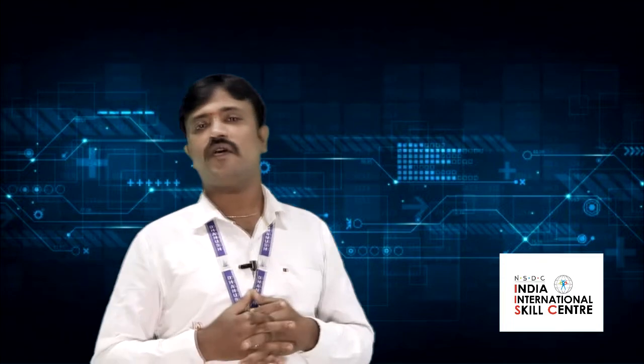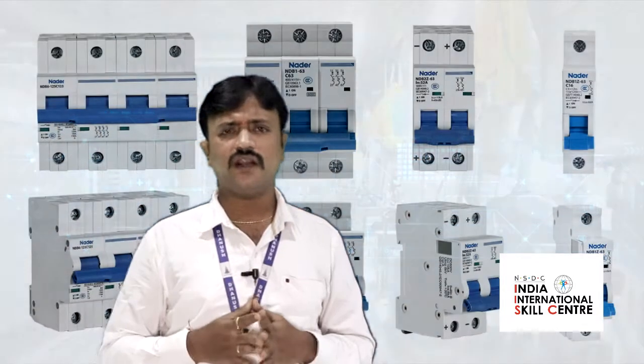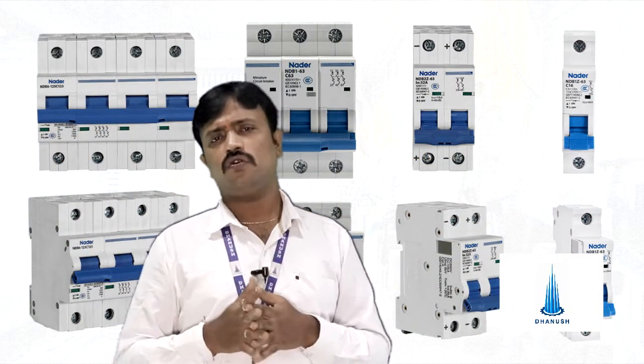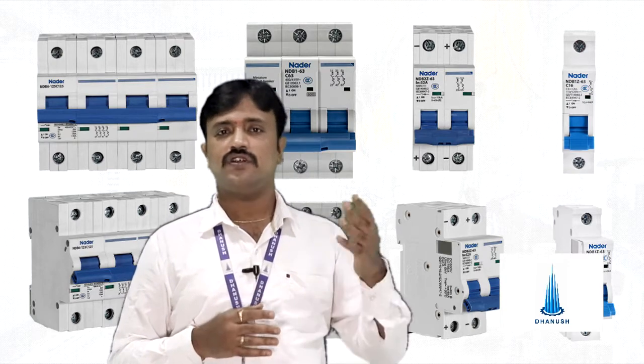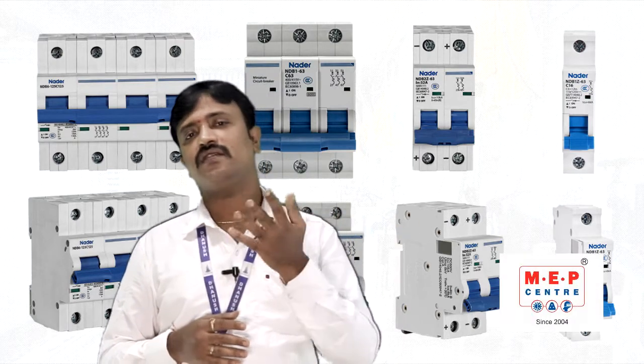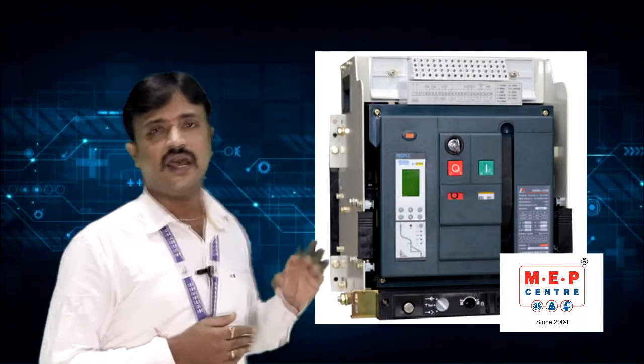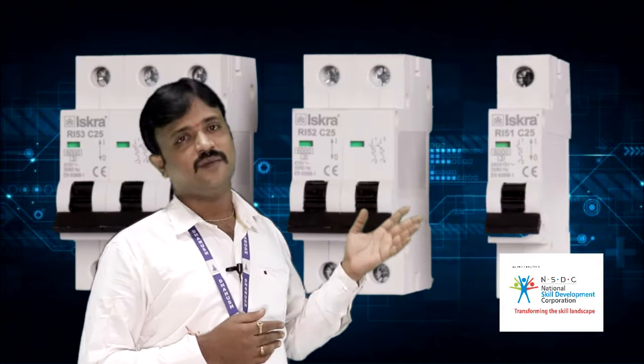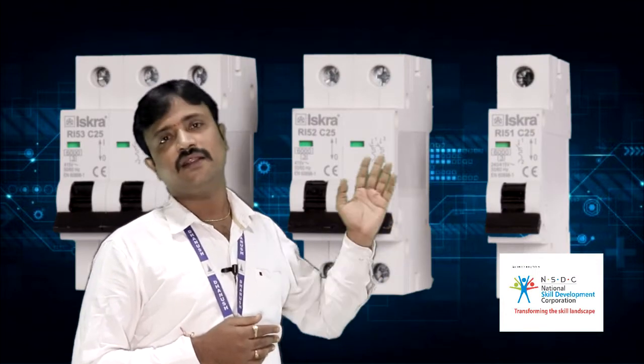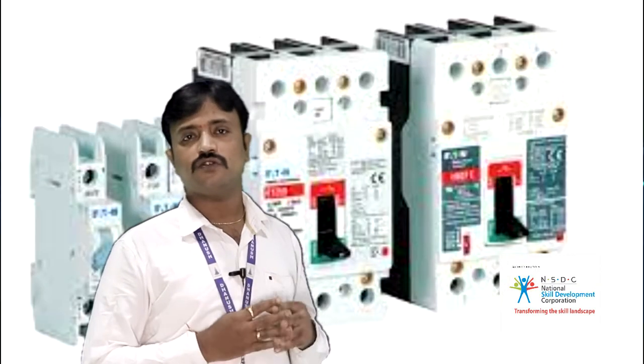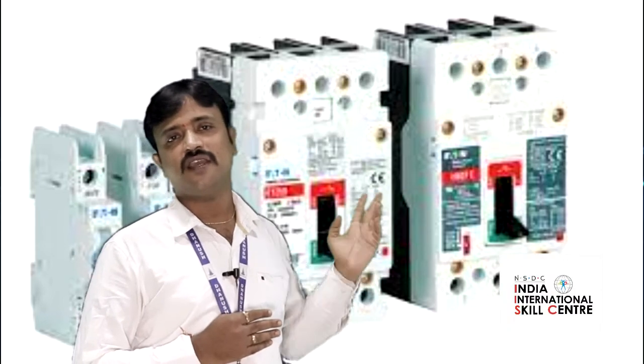And the next most important parameter is circuit breakers. Now, when coming to circuit breakers, we all know that they are classified into three categories. First one is HT side, second one is LT side, and the third one is protective circuit breaker. In the HT side, we have ACB, VCB, as you can see. The next is LT side, where we have MCB, MCCB, and ACB. And in the protective circuit breakers, we have three types: ELCB, RCBO, and RCCB.